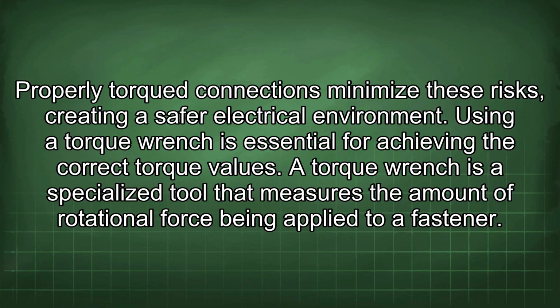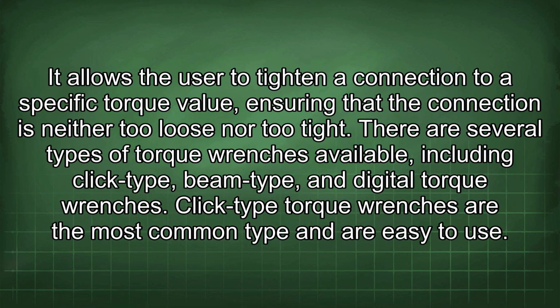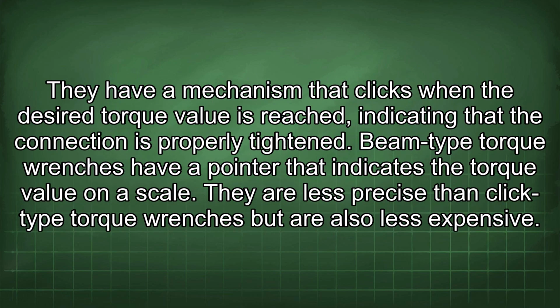Using a torque wrench is essential for achieving the correct torque values. A torque wrench is a specialized tool that measures the amount of rotational force being applied to a fastener. It allows the user to tighten a connection to a specific torque value, ensuring that the connection is neither too loose nor too tight. There are several types of torque wrenches available, including click-type, beam-type, and digital torque wrenches. Click-type torque wrenches are the most common type and are easy to use. They have a mechanism that clicks when the desired torque value is reached, indicating that the connection is properly tightened.